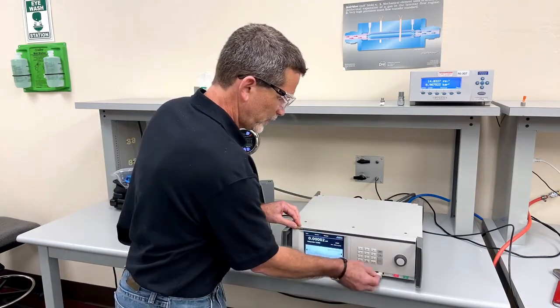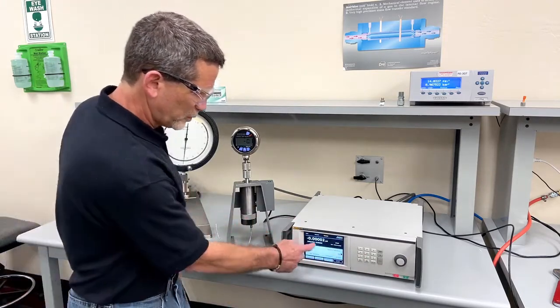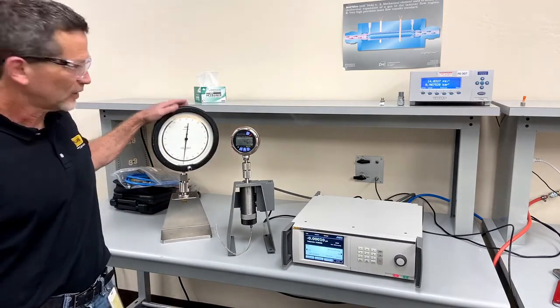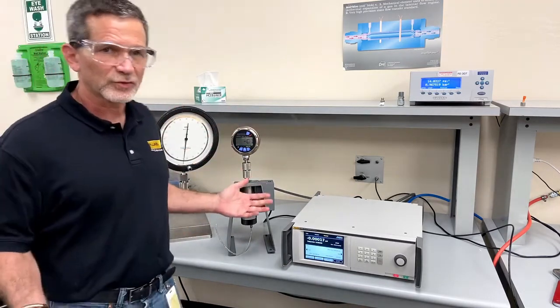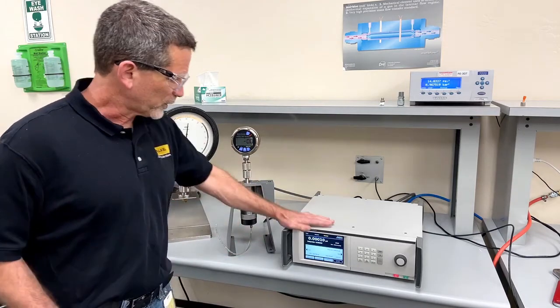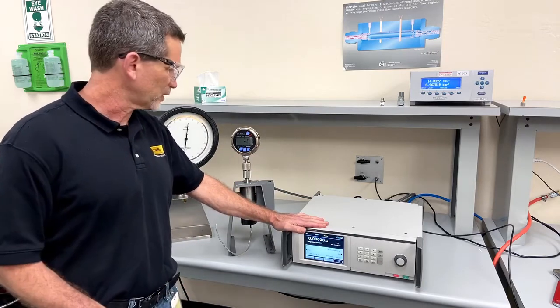We operate with all touch screen with various functions depending on where you press on the front panel, and typically we calibrate analog gauges, digital gauges, pressure transducers, or other instruments. The pressure controller will respond to your input by automatically setting the pressure.